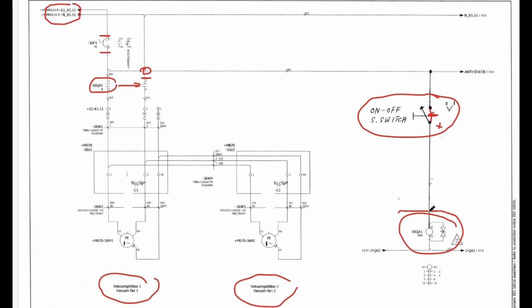Suppose the contact is okay, our contactor is on, but still our circuit is not running. When we check physically, we connect the meter here at A1 and A2, and we get 120 volt AC. It means the contactor is on and we are getting supply. Then again we see the contactor is on, but when we connect our positive probe here, still we are not getting supply. It means this contact of this magnetic contactor is damaged. So we will change that contactor, and then definitely our problem should be solved. After changing it, when we put the selector switch at the on position, the contactor is on, we check supply here with the positive and negative probes, we get 120 volt, and our problem is solved.